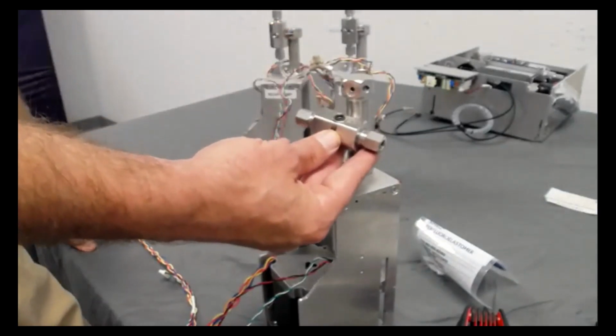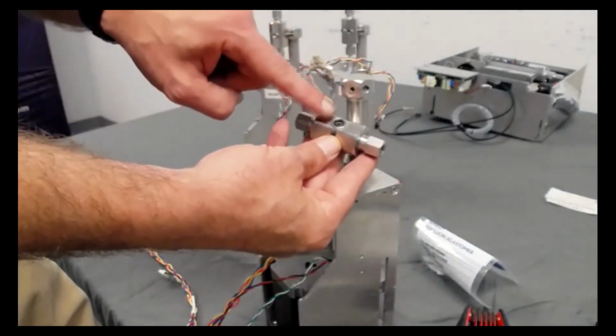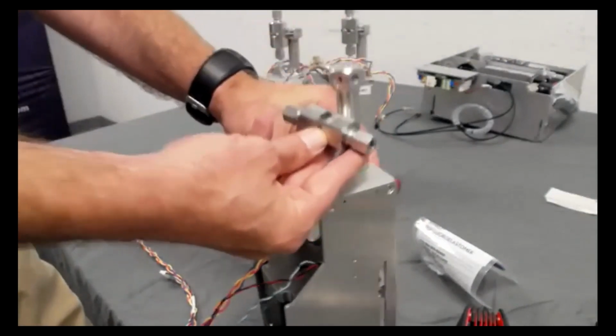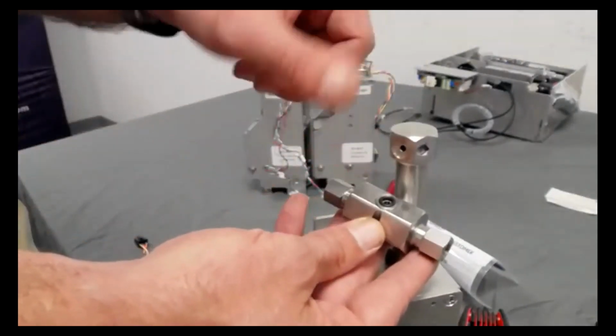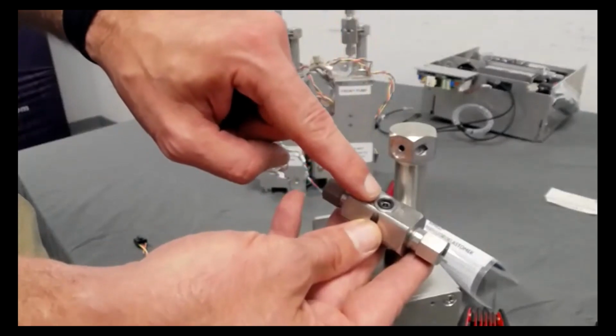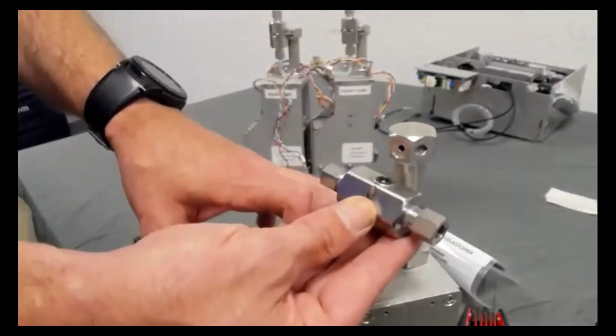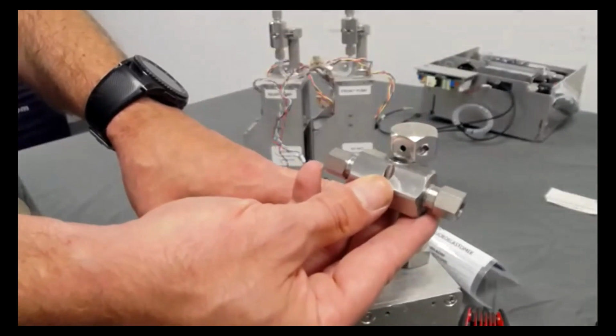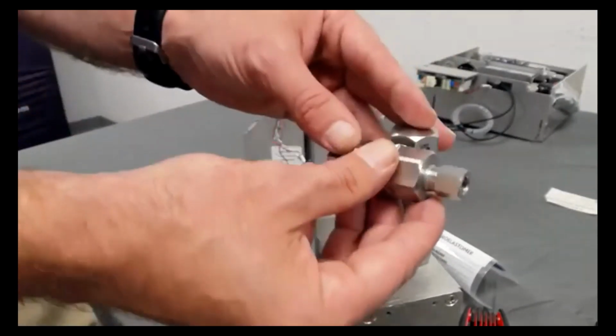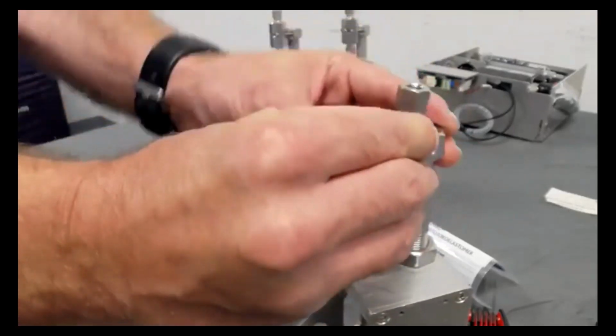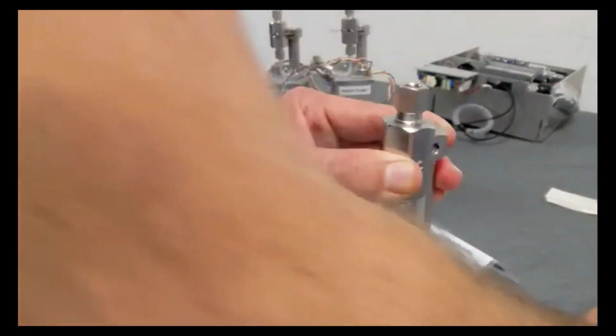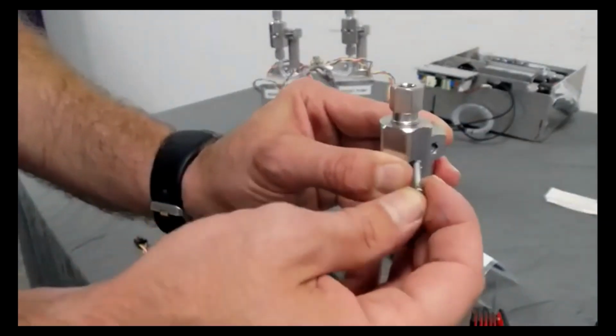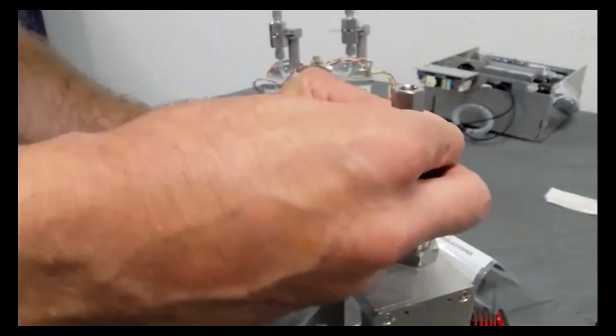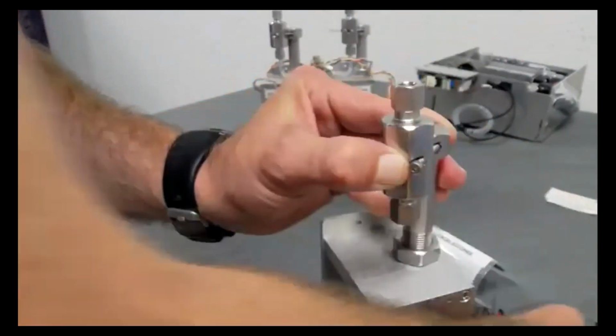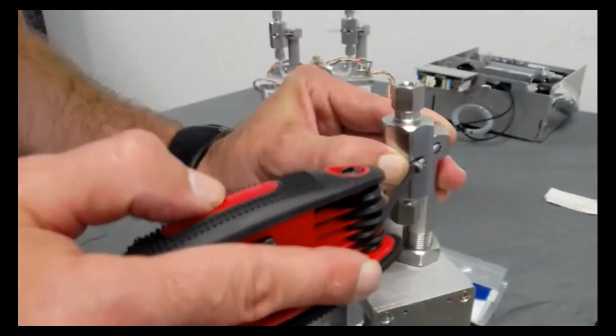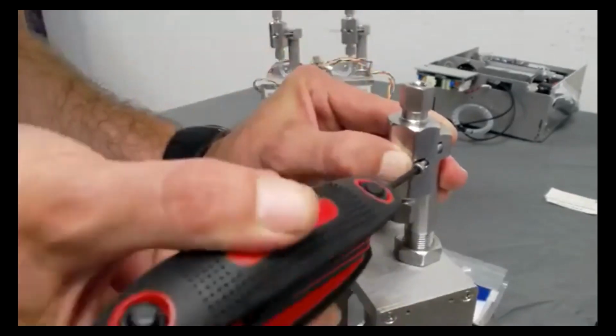Now here's the tricky part. You don't want to lose these when putting them back on, because this has to all sandwich together now. What I advise is, if you have a squeeze bottle, put a droplet of some kind of IPA on there, or do it the way I'm about to do it. I line up the holes with the check valve sideways, squish them together, and then turn it. With my free hand, I hold it there so that I can get a screw in. Make sure you keep that tension, and get that one screw pretty darn tight.